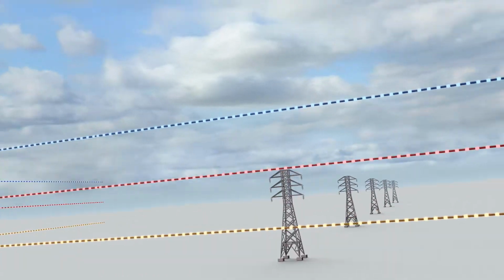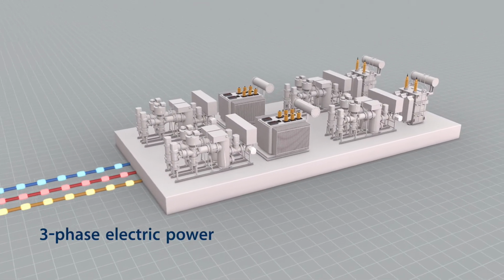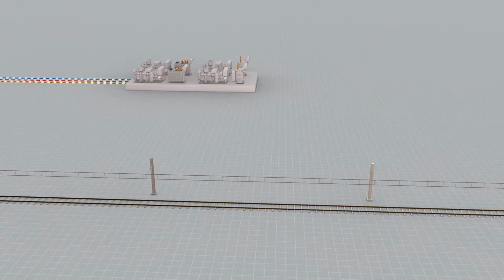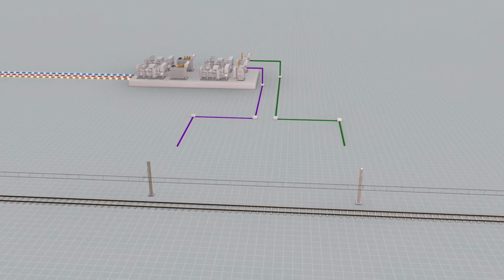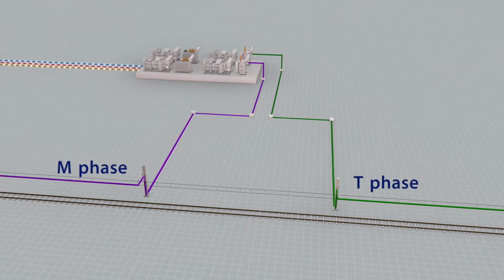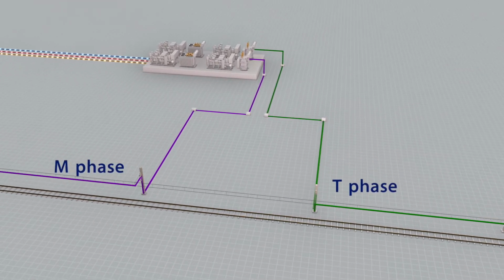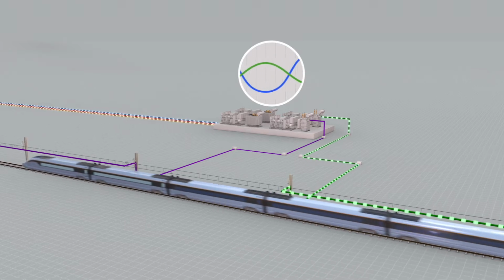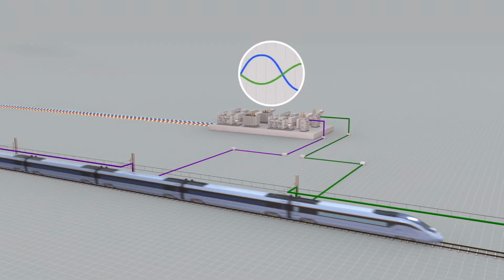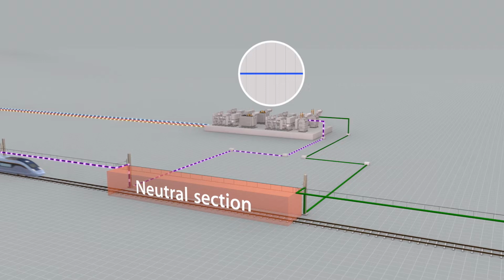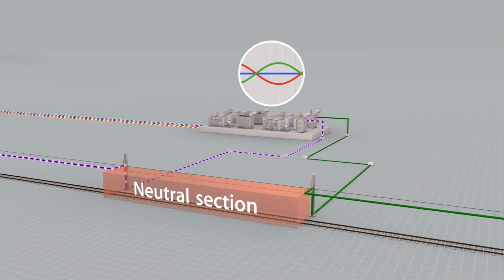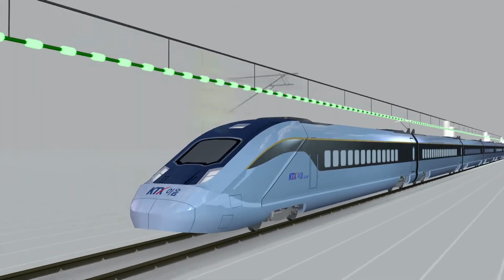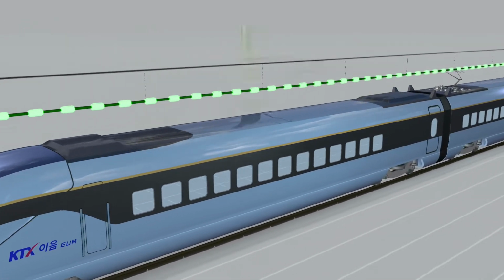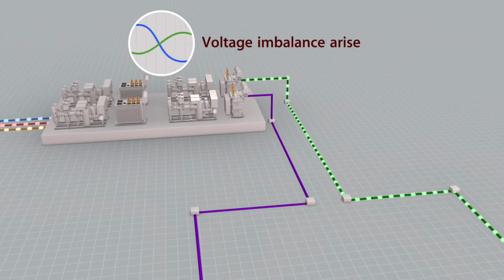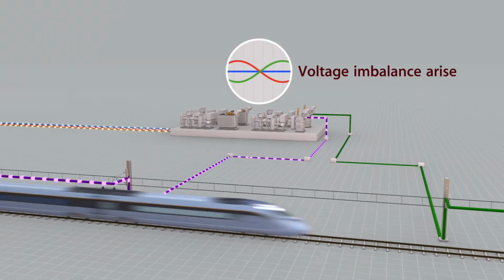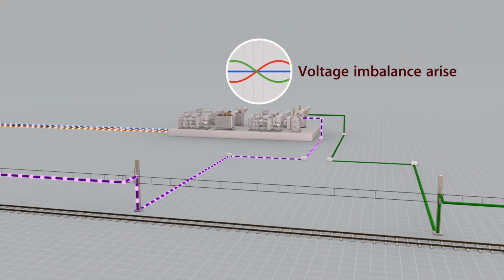Railway substations in Korea receive electric power from three-phase alternating currents. The electricity is separated into two single phases in the Scott transformer, and each is supplied in different directions. Since each of the two single phases has a different value, they cannot be connected and used, so an insulated section is essential. If electric power from only one single phase fully covers railway trains, a severe voltage imbalance arises in the three-phase side.